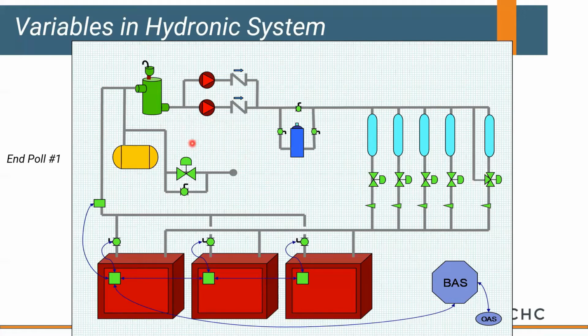Annual maintenance required. Yeah, that's not really an advantage. We'll get towards the end of the presentation and talk about why maintenance is important. Better situated to handle fluctuations within gas pressure. This is kind of a loaded question, so forgive me. I wasn't trying to bait you on this, but most modulating boilers can deal with fluctuating gas pressure, but to maintain good combustion, we really want a fixed gas pressure into that boiler. So 7 to 8 inches is typical. That's why we're trying to review turn down, and hopefully my little example made some sense. If not, let's deal with that in the Q&A.